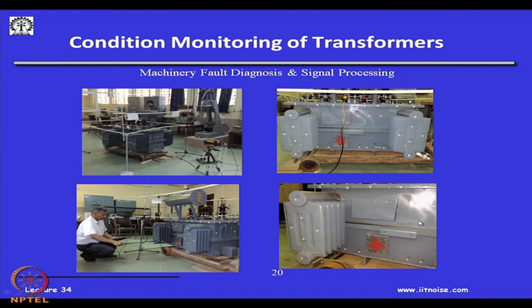Heat has to be dissipated, and that is why there are fins. You will have seen in many transformers there are tubings which carry nothing but oil, and this is a tank wherein oil is there. You would have heard of scenarios where there was a power outage because of a transformer burst. Why did that burst happen? Because the transformer was dry; the maintenance crew had not ensured that the level of the oil was maintained, and that is the reason why transformers burst.